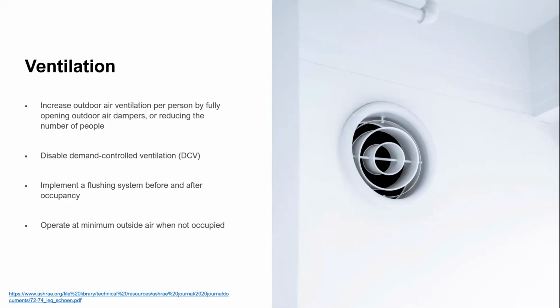Implement a flushing system before and after occupancy. This is operating the ventilation system 2 hours before and after occupancy. So if your office opens at around 8 a.m., then you should turn on your ventilation system, just the ventilation system, not the air conditioning, by 6 a.m. and keep it running 2 hours after.